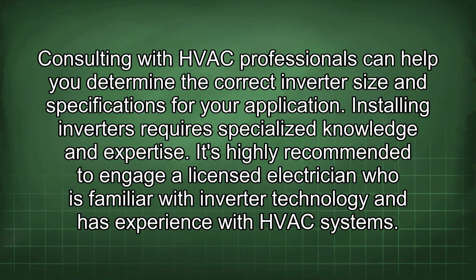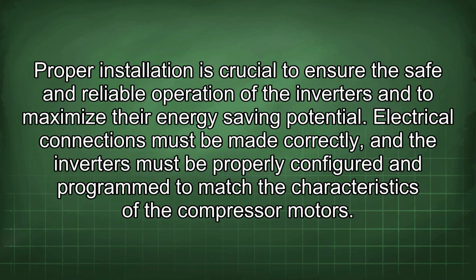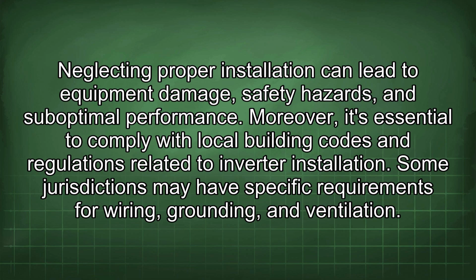Installing inverters requires specialized knowledge and expertise. It's highly recommended to engage a licensed electrician who is familiar with inverter technology and has experience with HVAC systems. Proper installation is crucial to ensure the safe and reliable operation of the inverters and to maximize their energy-saving potential. Electrical connections must be made correctly, and the inverters must be properly configured and programmed to match the characteristics of the compressor motors. Neglecting proper installation can lead to equipment damage, safety hazards, and suboptimal performance.